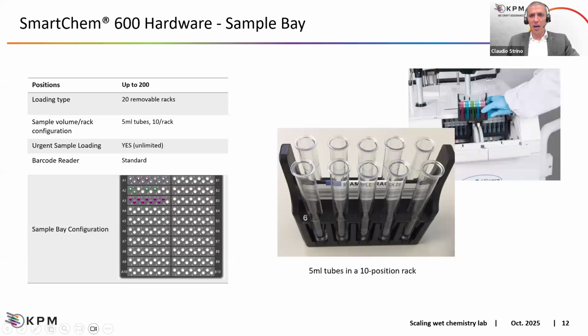This is a hardware overview where we can see, as we said, that we have 2 sample carousels. We can load on board 200 samples because we have 20 removable racks with the possibility to host 10 samples each. Urgent sample loading, yes, because on the ongoing routine or when adding new samples to the ongoing routine, we can add urgent samples at any time. And with 5 ml available for each one, we can cover a really huge set of parameters considering that we are working in microliters for each test.